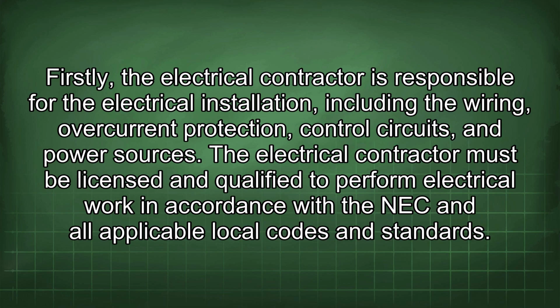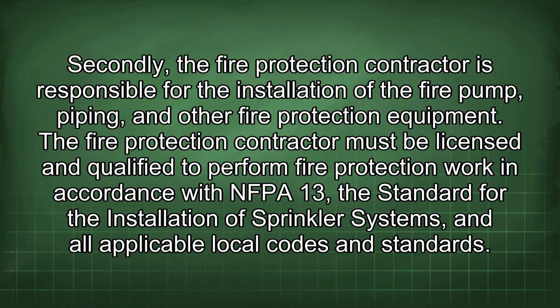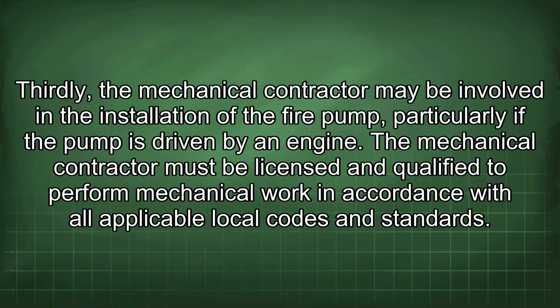Secondly, the fire protection contractor is responsible for the installation of the fire pump, piping, and other fire protection equipment. The fire protection contractor must be licensed and qualified to perform fire protection work in accordance with NFPA 13, the standard for the installation of sprinkler systems, and all applicable local codes and standards. Thirdly, the mechanical contractor may be involved in the installation of the fire pump, particularly if the pump is driven by an engine. The mechanical contractor must be licensed and qualified to perform mechanical work in accordance with all applicable local codes and standards.